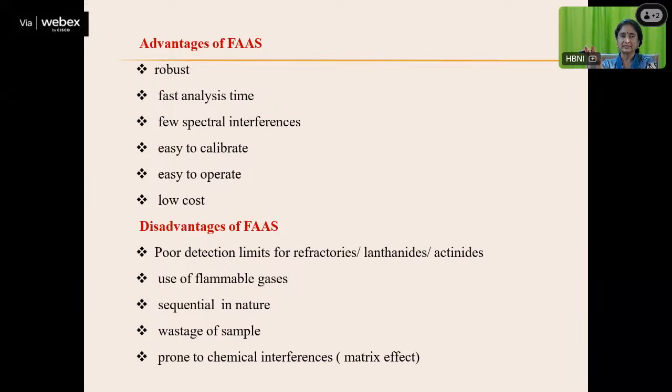Use of flammable gases: some accident may happen if you are not very careful. Then it is sequential in nature, meaning one element at a time, because for a particular analyte you have a dedicated hollow cathode lamp. So one by one, each analyte you have to do. That is a big disadvantage nowadays, when everything is fast moving, so sequential analysis is not desirable.